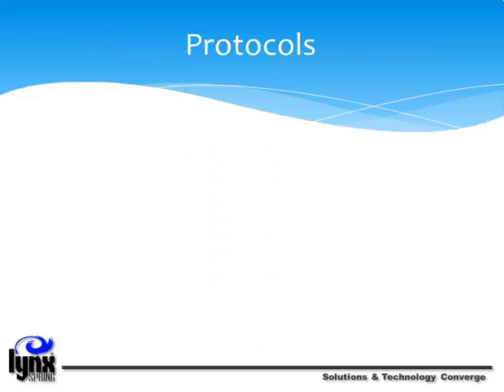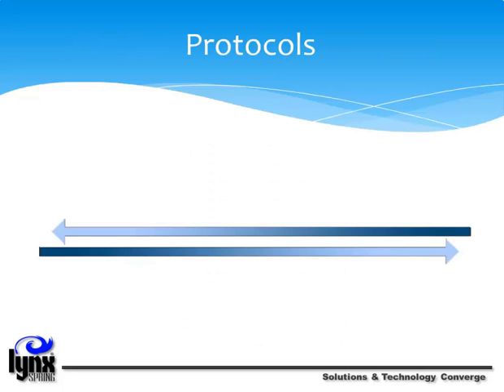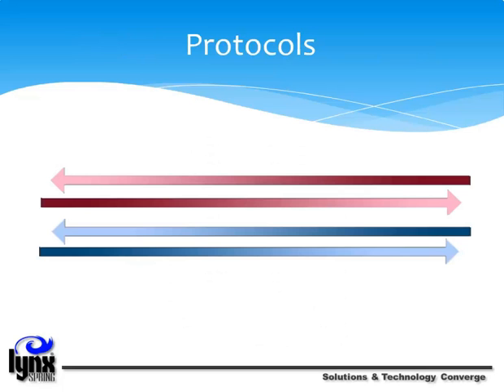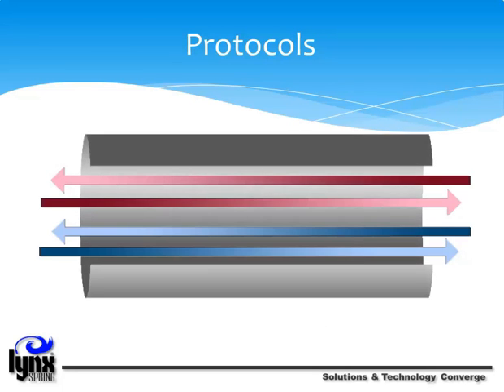Protocols are standards that allow computers to communicate. A protocol defines how computers identify one another on the network, the form the data should take in transit, and how this information is processed once it reaches its final destination. Protocols also define procedures for handling lost or damaged transmissions or packets. TCP/IP, IPX for Novell Netware, and AppleTalk for Macintosh computers are the main types of network protocols in use today. Building automation systems use their own protocols, such as BACnet, LonWorks, and Modbus. Although each network protocol is different, they all share the same physical cabling. This common method of accessing the physical network allows multiple protocols to peacefully coexist — a concept known as protocol independence.